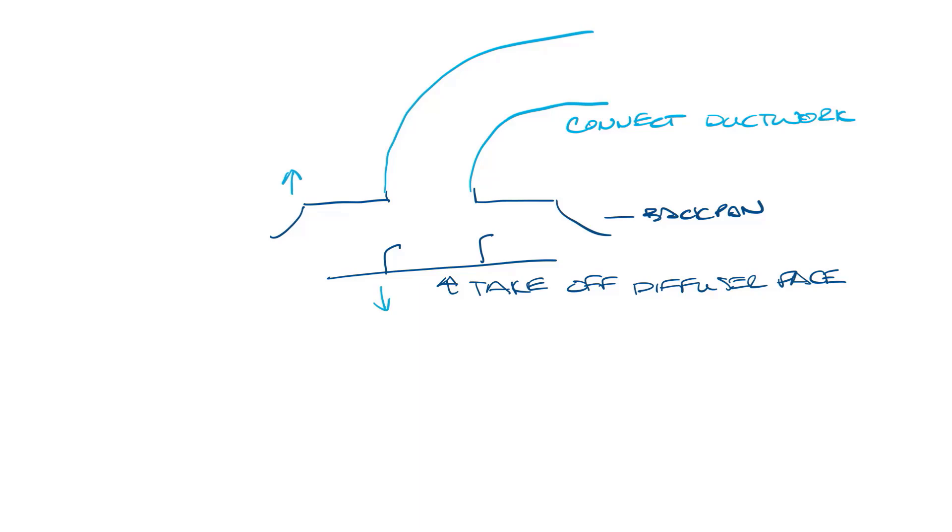So let's slide this out of the way and look at what you need to do to install the diffuser. So let's draw a diffuser first. This is the backpan of the diffuser and this is the face. First of all you want to take the face off the diffuser and then you want to connect the ductwork. Then you want to put the diffuser up in the ceiling so that the edge of the diffuser backpan is flush with the sheetrock.